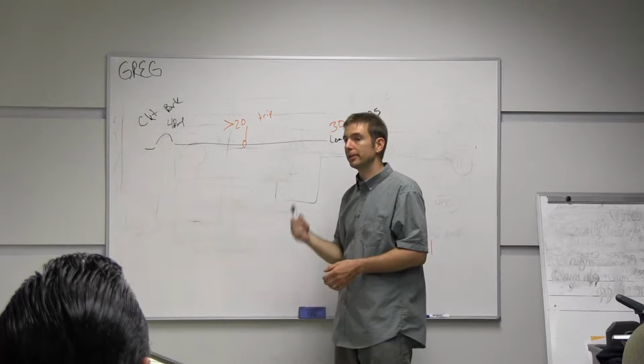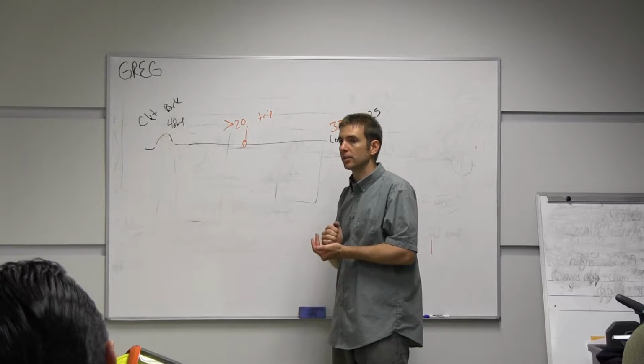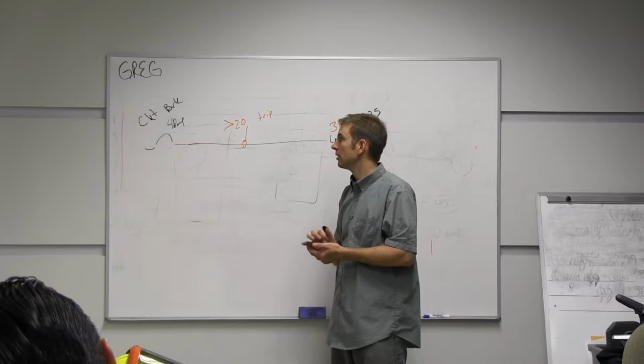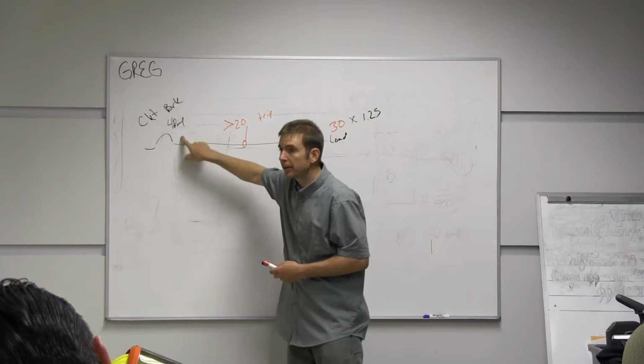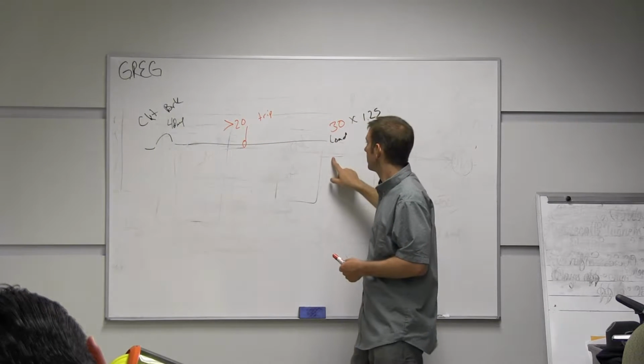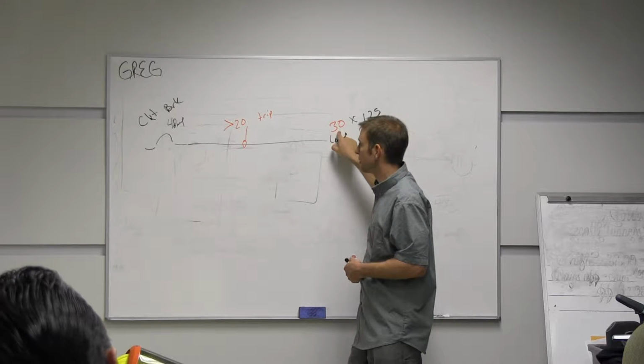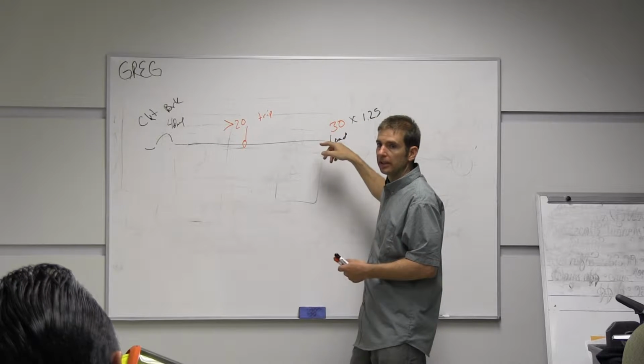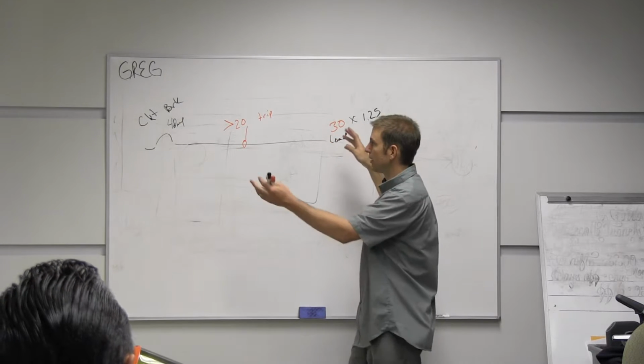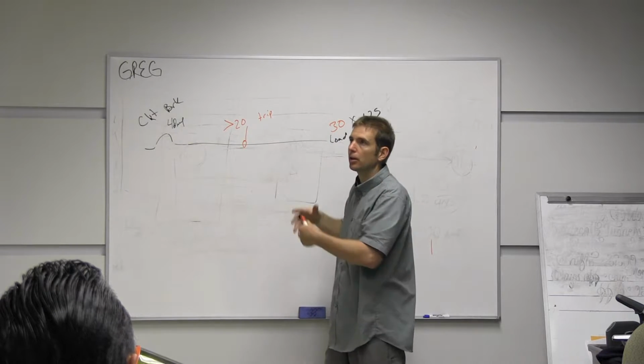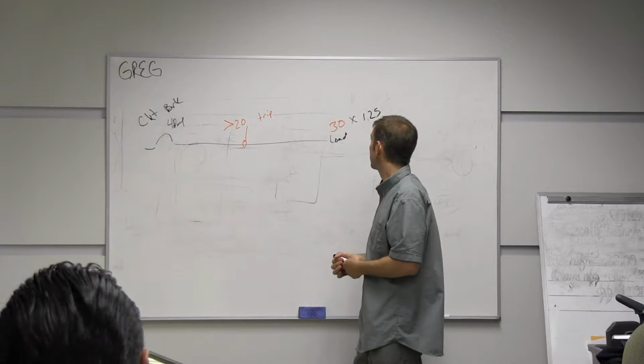So would I have to go up to the number 8 American wire gauge conductor? So yes, our circuit breaker protects our wire, and our wire handles the load. So whatever your load is, your wire needs to match, and whatever circuit breaker, it all has to be cohesive, I guess is the word.